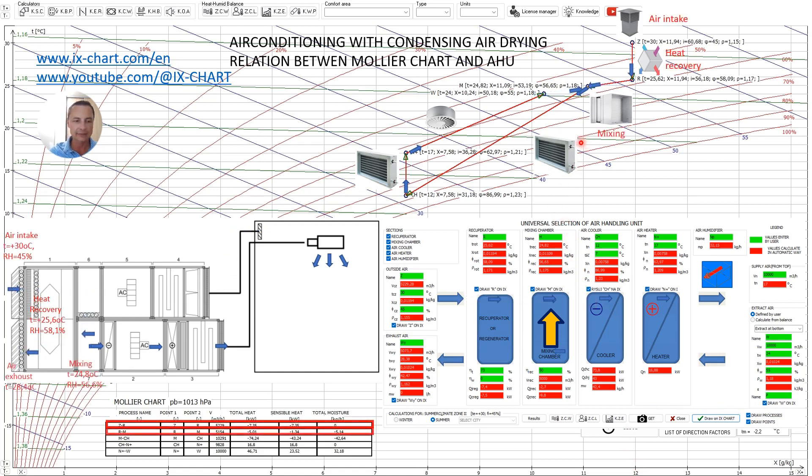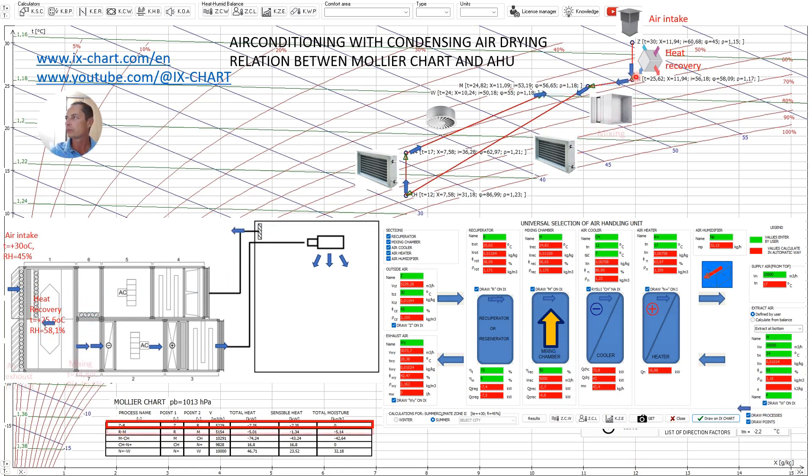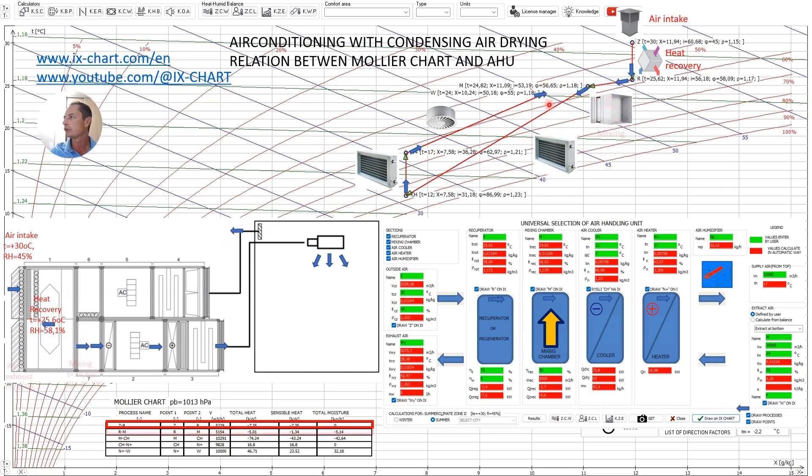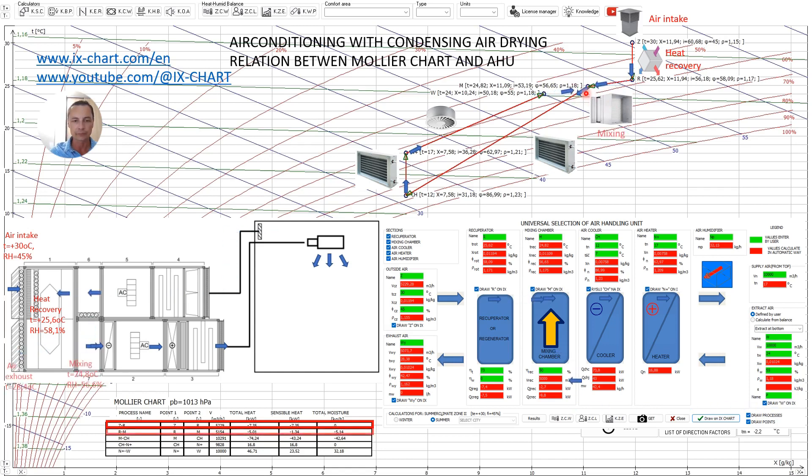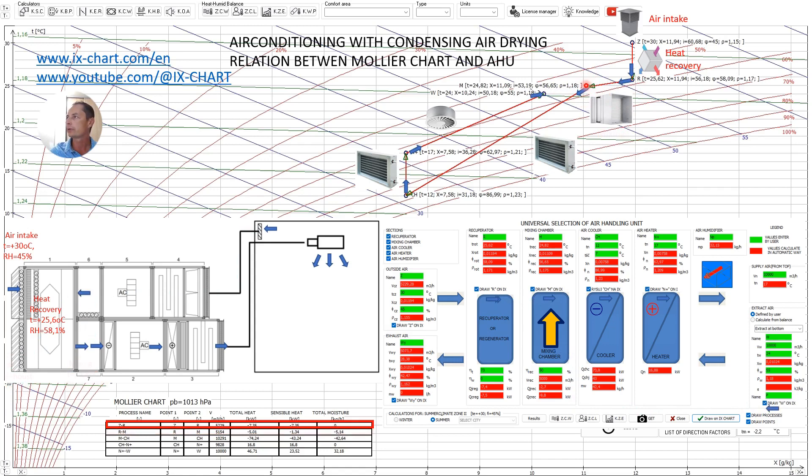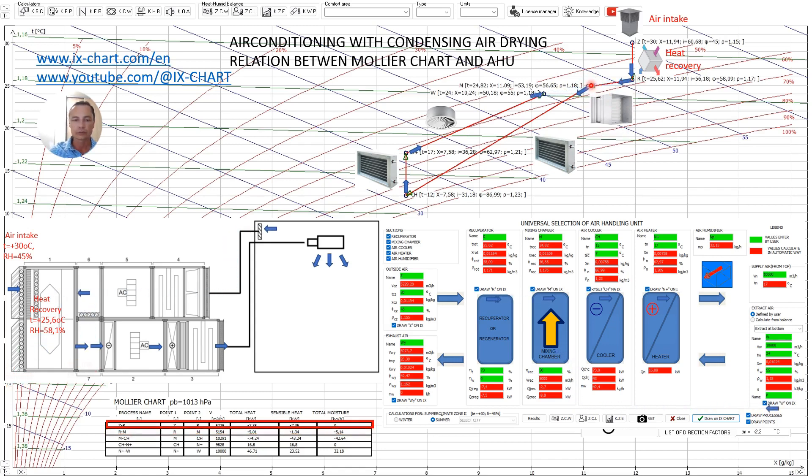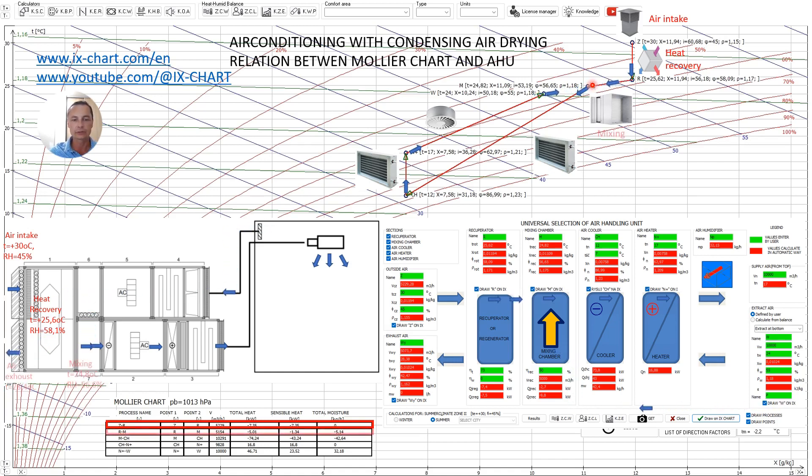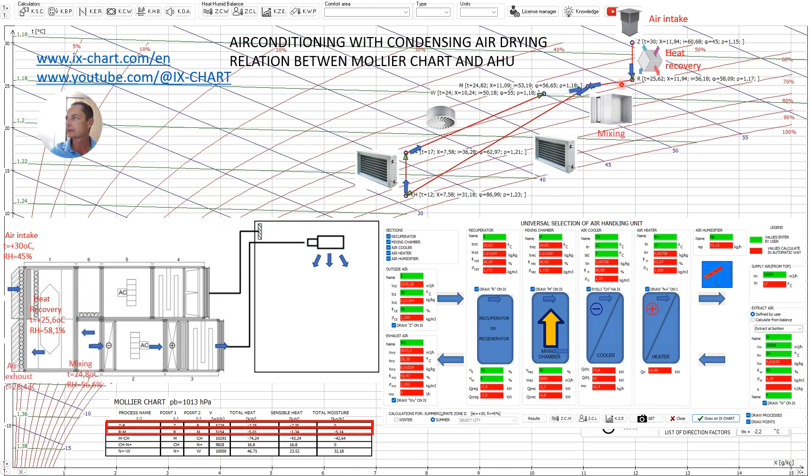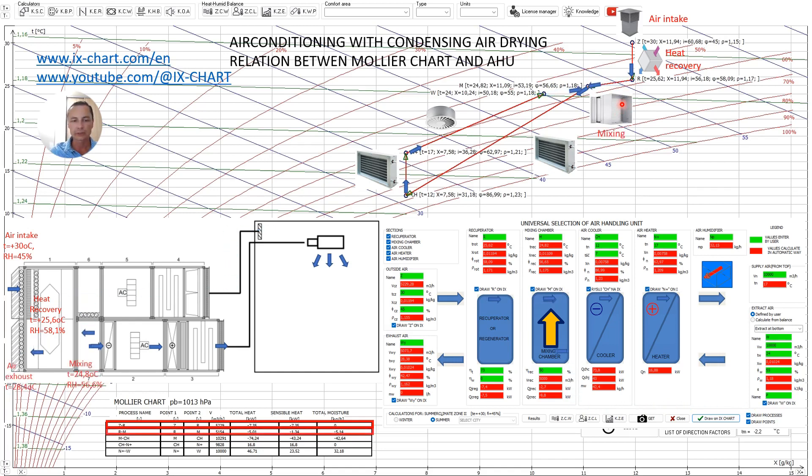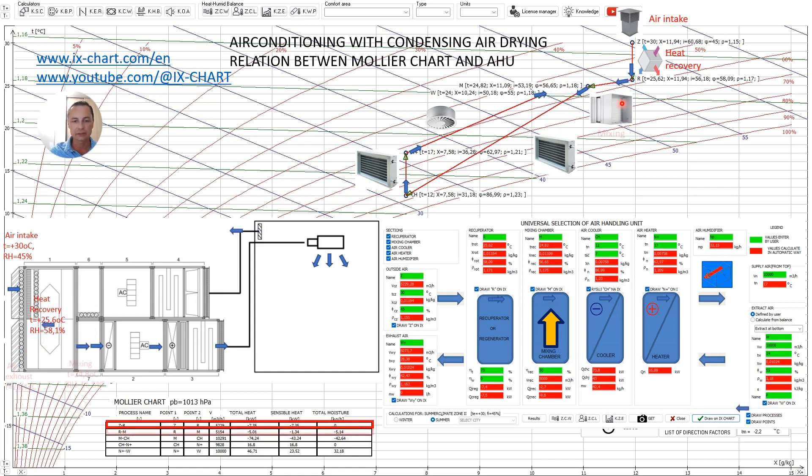In the next step the air flows through the mixing chamber from point V to point M and from point R to point M. Localization of this point M depends on mixing ratio and generally the mixing chamber is an empty section with two dampers and the ratio of mixing depends on their settings. Here I assume 50% as I said before but in other cases it could be a different number as well.